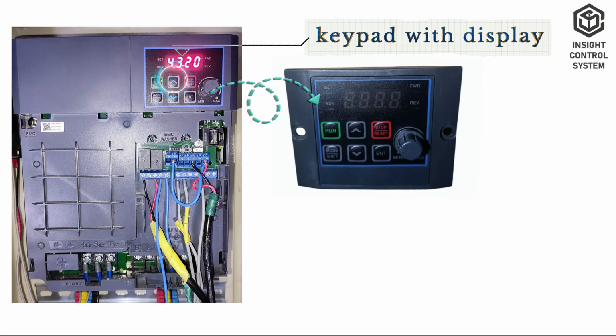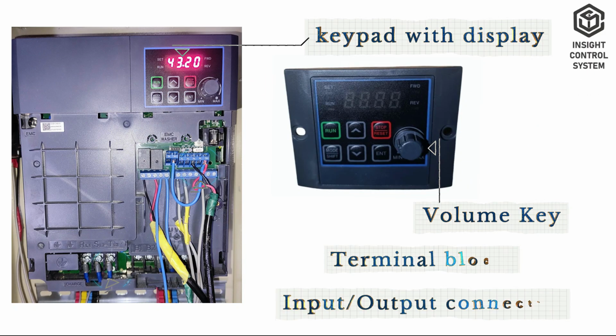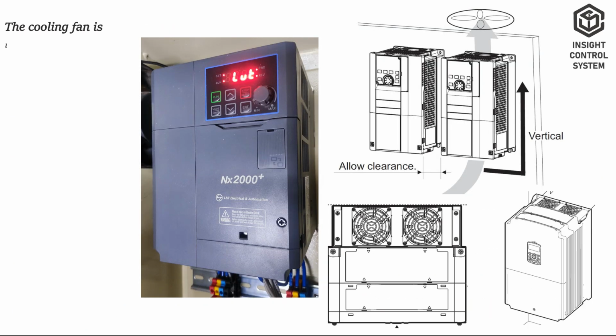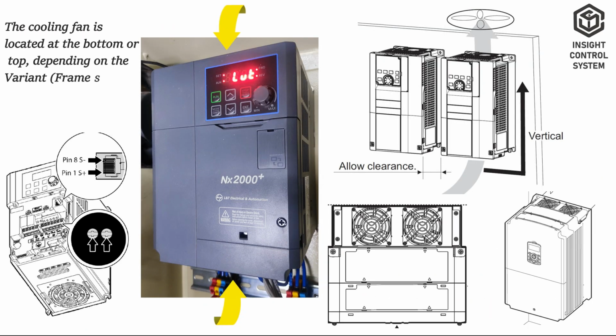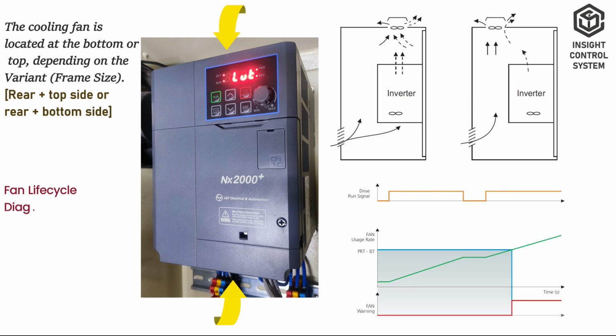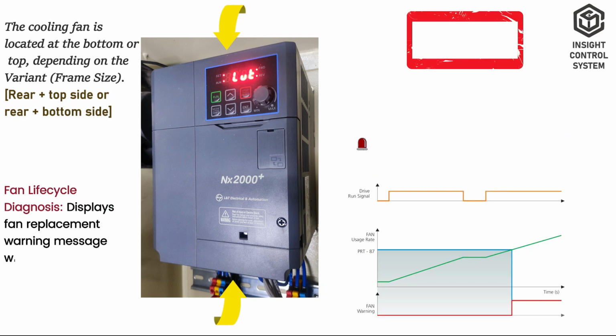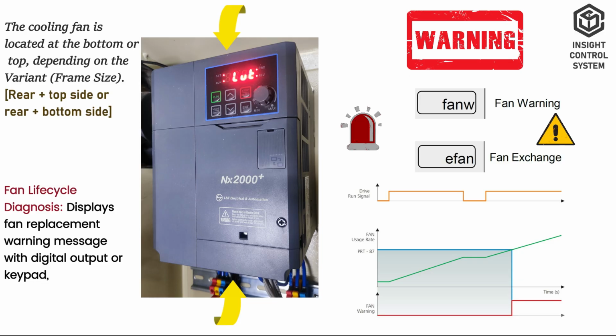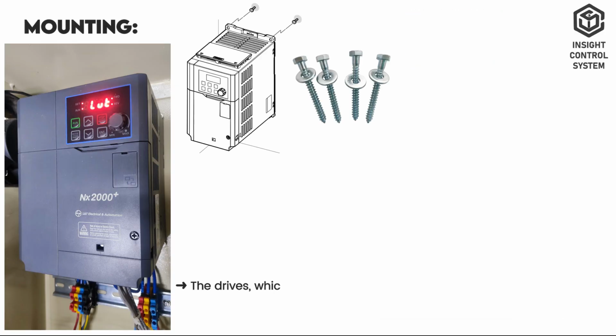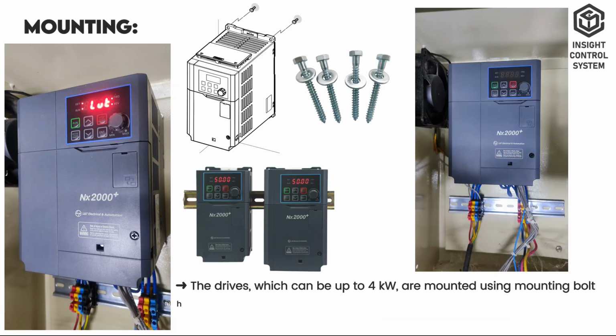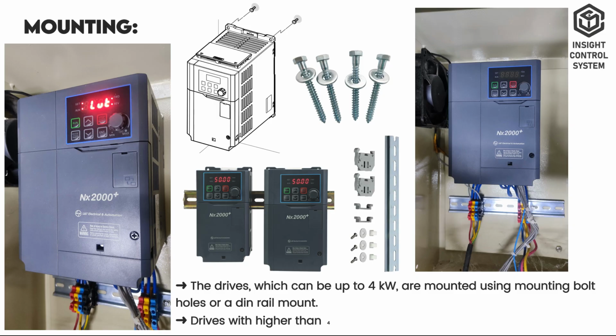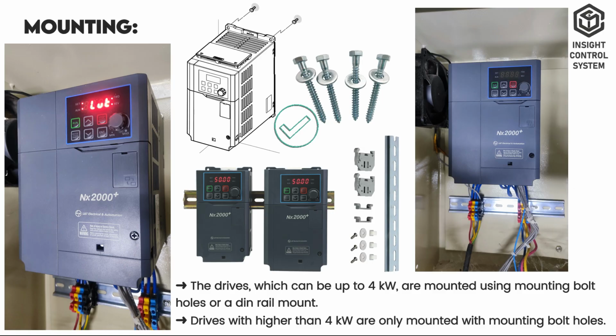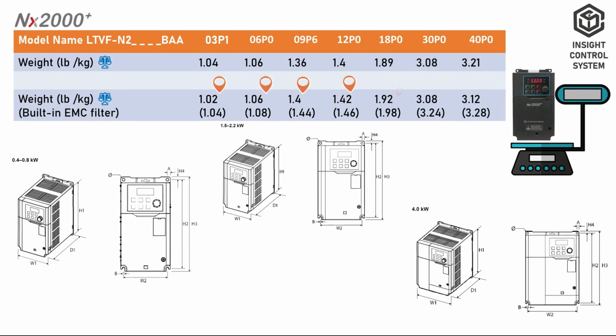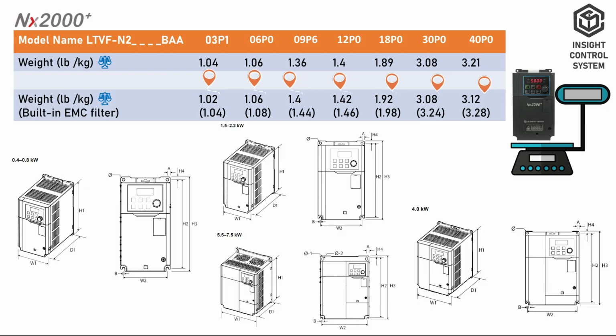This is keypad with display. This is volume key. This is the terminal blocks. The cooling fan is located at the bottom or top, depending on the model. Fan life cycle diagnosis. Displays fan replacement warning message with digital output or keypad. Mounting. The drives, which can be up to 4 kilowatts, are mounted using mounting bolt holes or a DIN rail mount. Drives with higher than 4 kilowatts are only mounted with mounting bolt holes. The weight ranges from 1.04 to 3.28 kilograms, depending on the drive model.